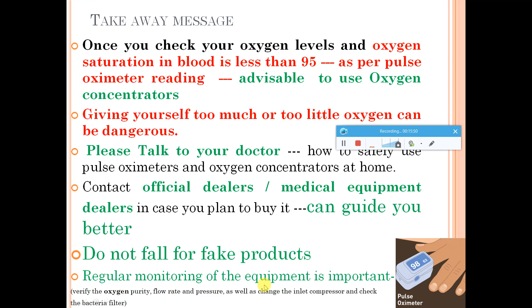So we know there are oxygen concentrators, there are filters inside. So there is a chance that they can get contaminated. There can be biofilm growth on that, and various other issues can happen because our air is not pure. There can be certain organisms in the air itself. So there has to be regular monitoring of this equipment. So you have to verify the oxygen purity, the flow rate, the pressure, and various other filters there, so that there is no issue. Okay, so regular monitoring of this equipment has to be done so that the equipment efficiency is good enough and you can use it for the expected life, that is 4 to 7 years.